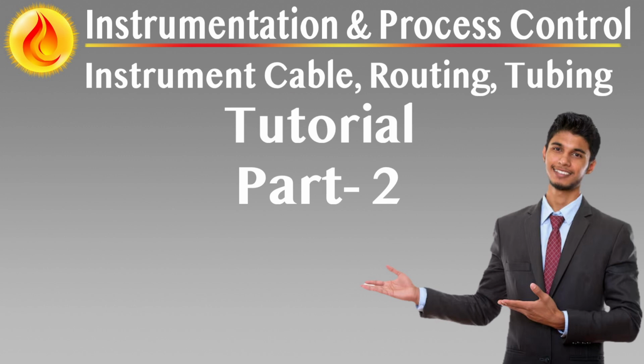Cables must always enter from below or drop below the gland before entry. Glands must not be installed at the top of instruments or junction boxes. Clamping or anchoring below the gland is required to eliminate mechanical stress on the seal. Special purpose glands are required where signal cables enter hydrocarbon-filled environments, e.g. rotating equipment sensors.